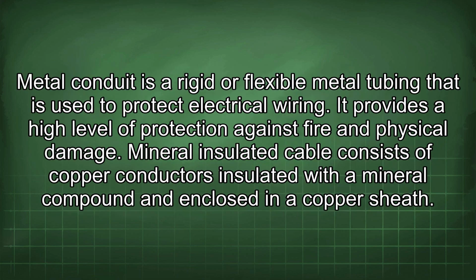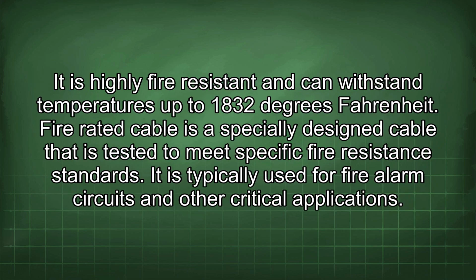Metal conduit is a rigid or flexible metal tubing that is used to protect electrical wiring. It provides a high level of protection against fire and physical damage. Mineral insulated cable consists of copper conductors insulated with a mineral compound and enclosed in a copper sheath. It is highly fire resistant and can withstand temperatures up to 1832 degrees Fahrenheit. Fire-rated cable is a specially designed cable that is tested to meet specific fire resistance standards. It is typically used for fire alarm circuits and other critical applications.